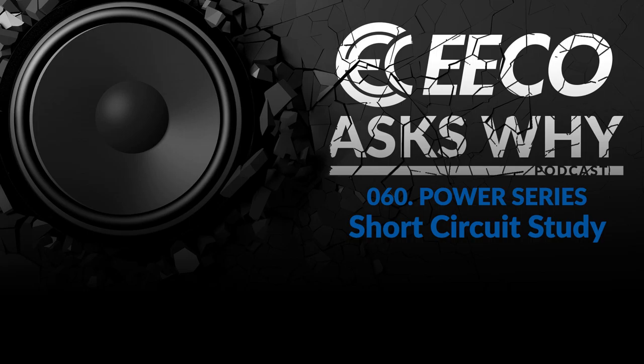So I think the why would be a short circuit study is really needed to ensure that during a fault, also known as a short circuit, the protective devices are not subject to current levels and mechanical forces greater than they were designed to withstand. And thus, one, will not open, two, explode, or three, some other undesired result. So I would say the most important thing is to ensure that you're operating within the manufacturer's parameters for that device.